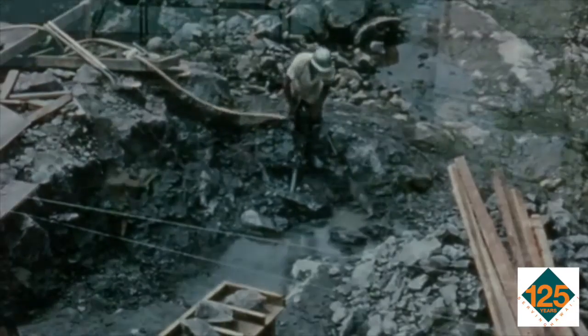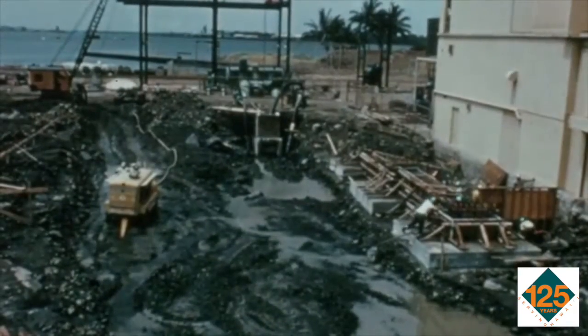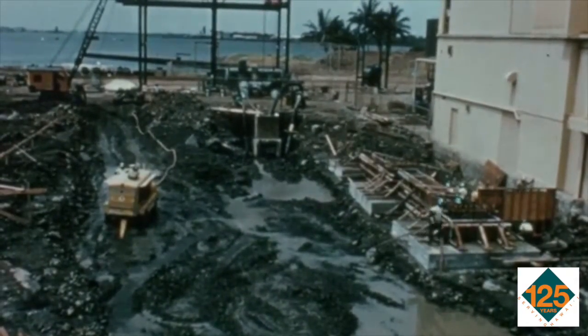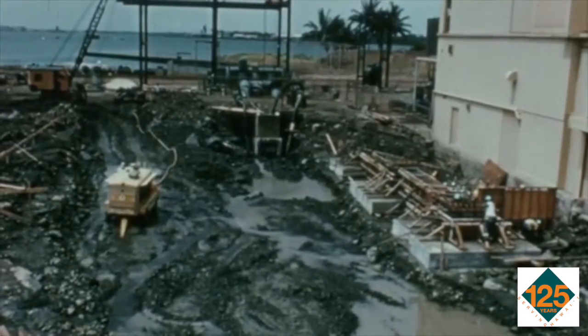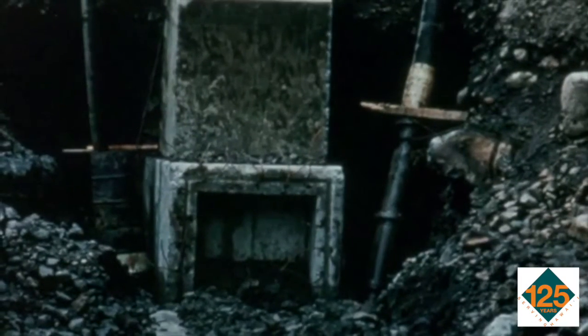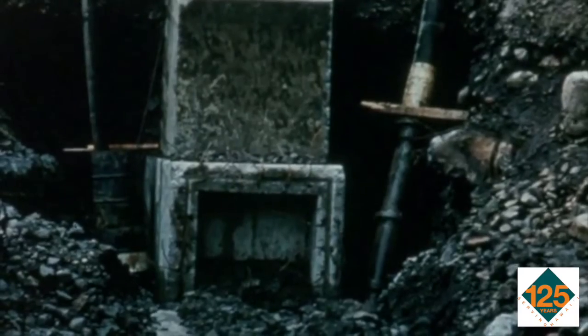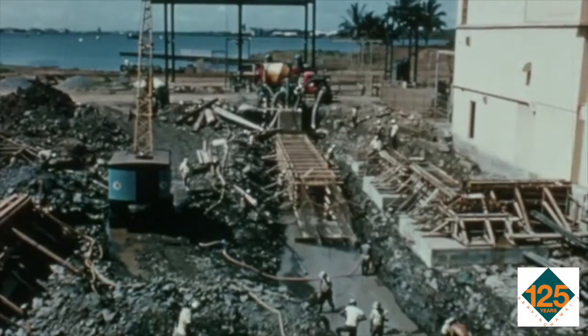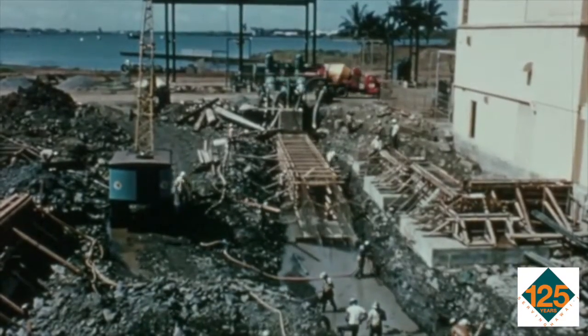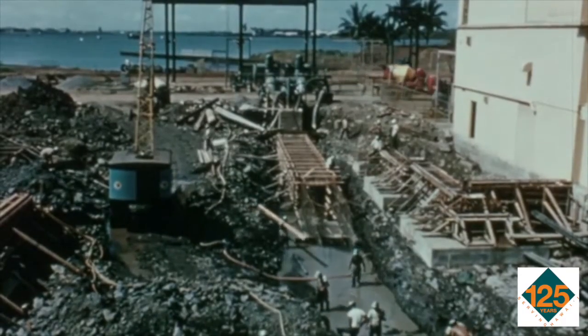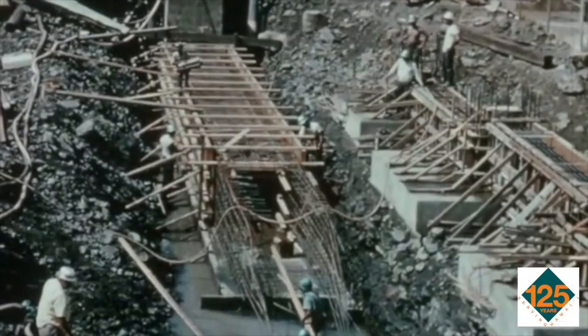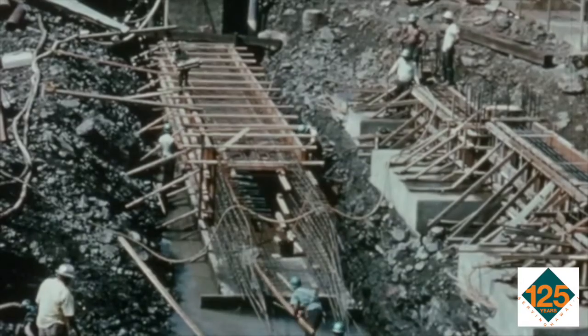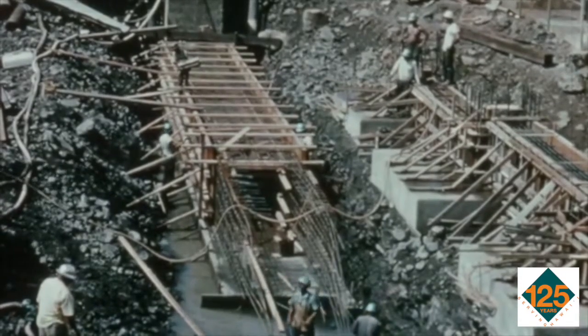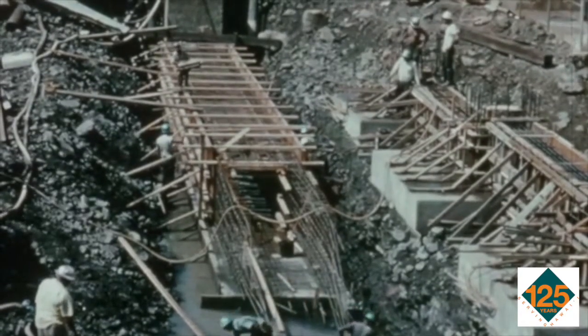The first step is the construction of the water tunnel, which carries as much as 55,000 gallons of salt water per minute to condense the large volumes of steam from the turbine. During the building, and before the tunnel was put into operation, it was tested by filling the tunnel with water and raising the pressure. This ensures a perfect seal between the pumps and the gigantic condenser.